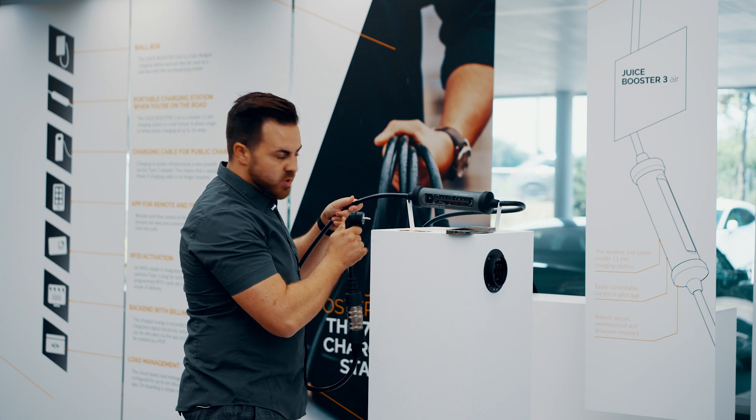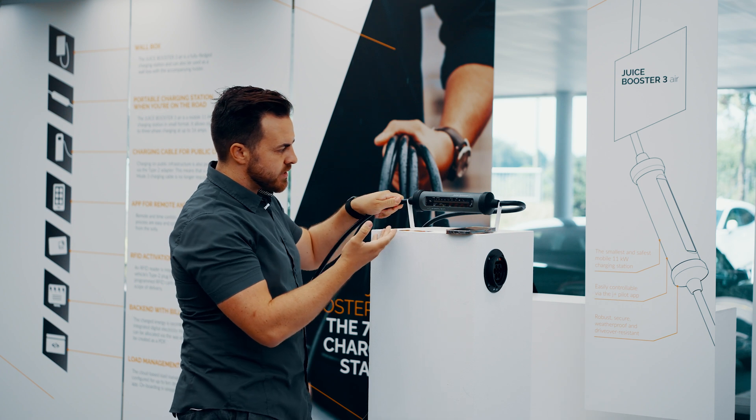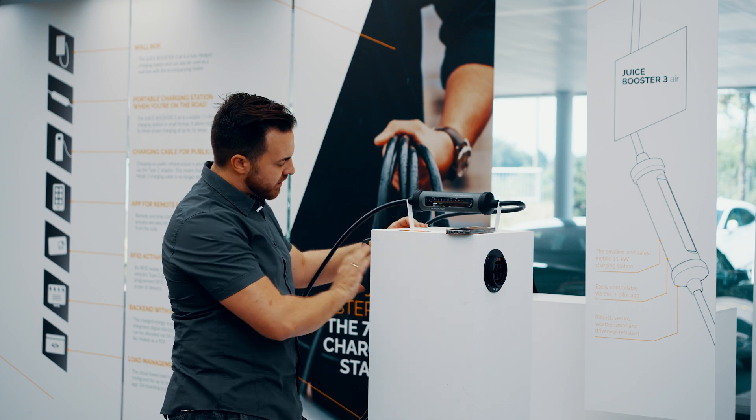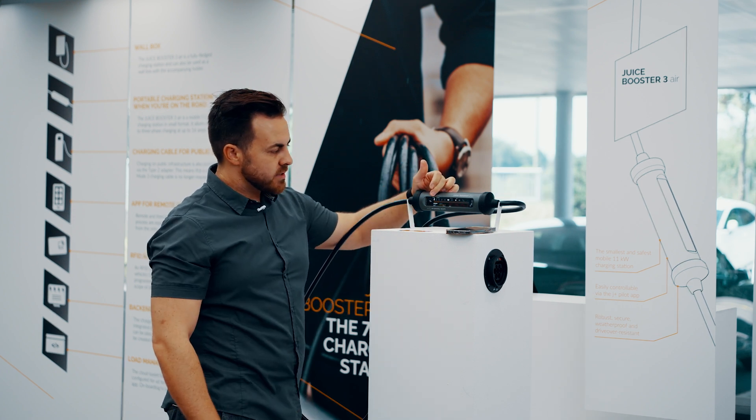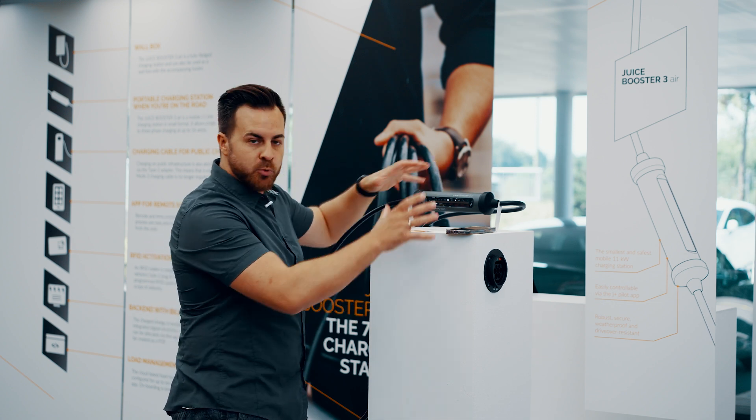I'll put the booster here so you can see it clearly. I now plug it into the socket, and what you see is that the booster is booting up. It checks the socket, sees that it is only one phase and that it can draw 13 amps from the Schuko type socket.